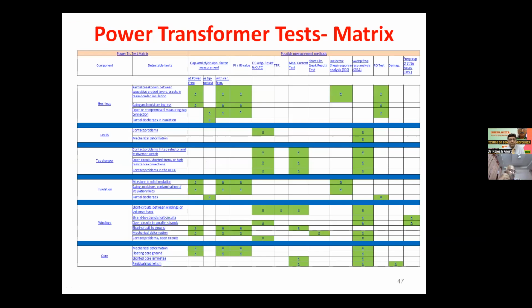So in transformers, as we saw in the very first slide, we have got different components. There is core, winding, insulation, multiple things. Now, when I say that my winding is healthy, I cannot say that based on only one test. I have to perform a number of tests to be sure that my winding is healthy. Similarly, for the overall complete transformer, we have to do so many tests and analyze so many reports at the same time to ascertain whether my transformer is healthy or not. Otherwise, we may lose the importance of one particular test.